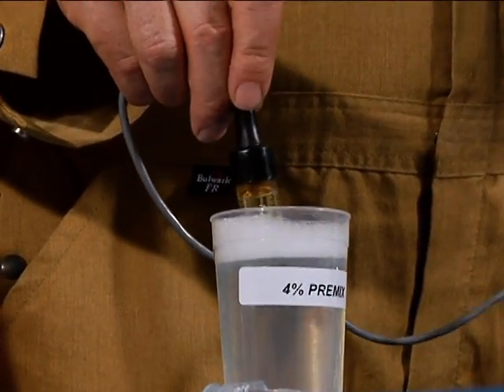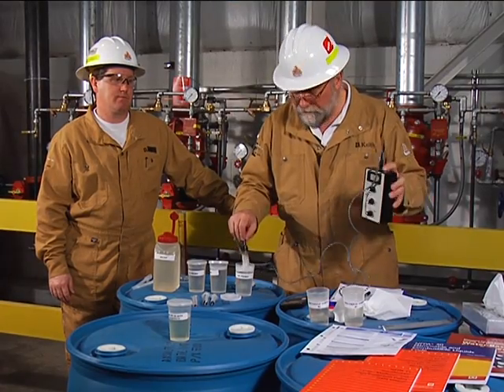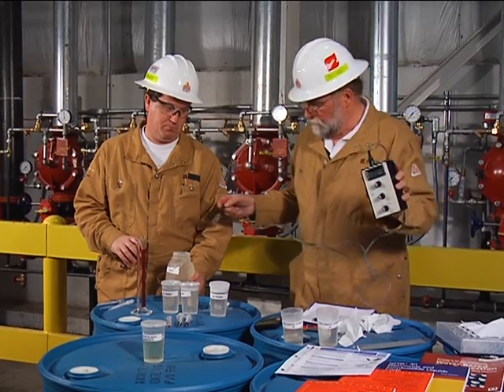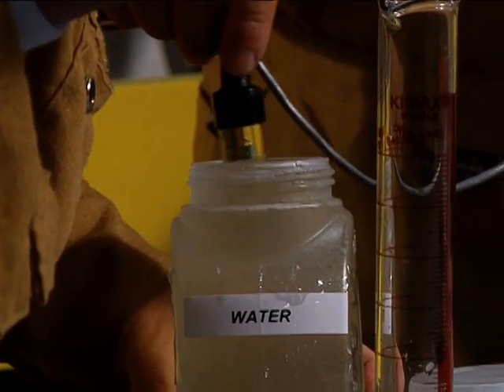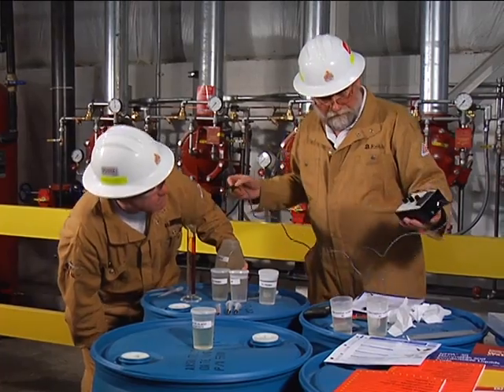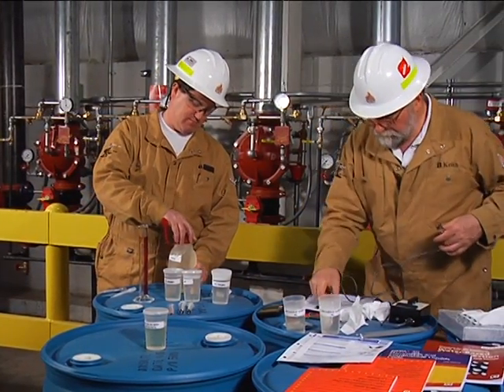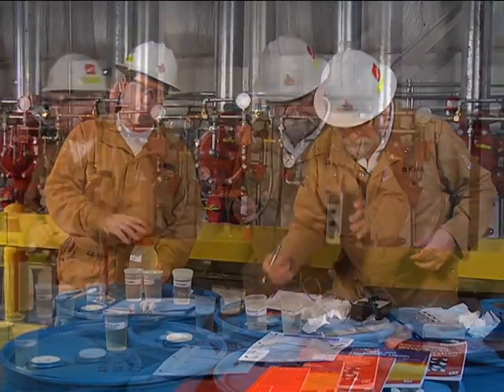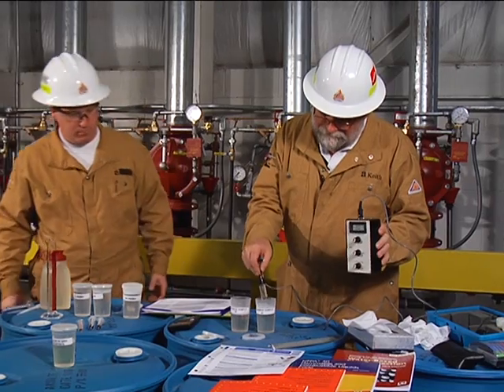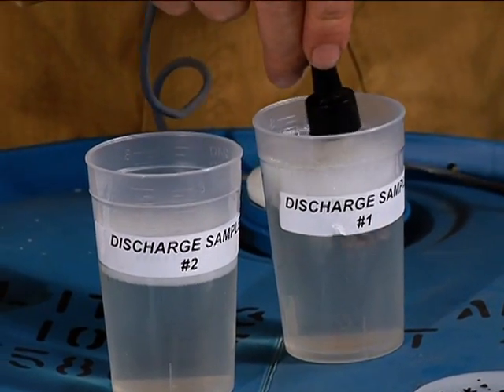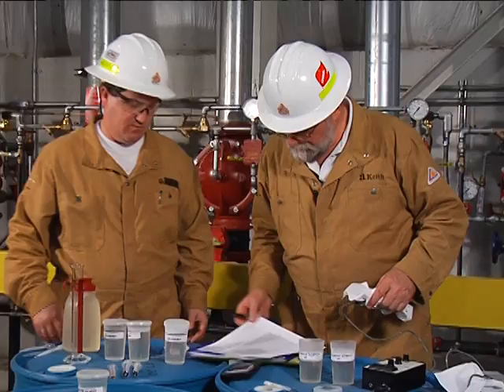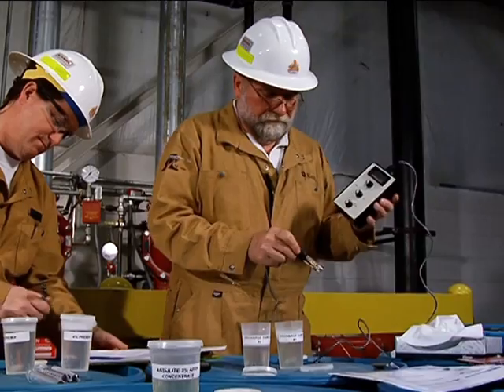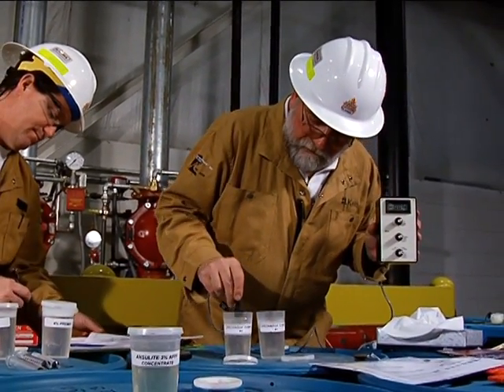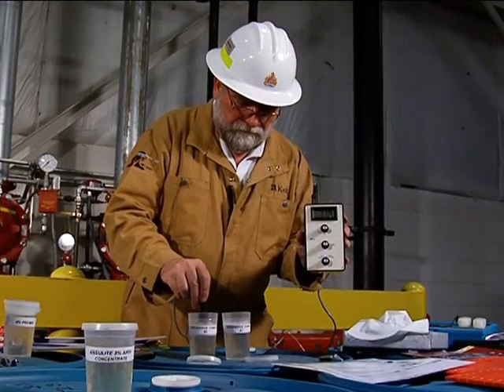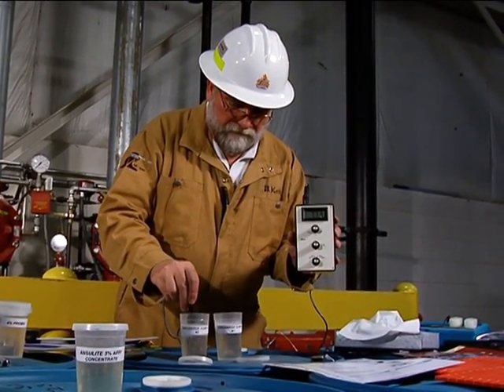And lastly, our 4% calibration standard. 8.90. 1.47. First discharge sample number 1. 7.75. Discharge sample number 2. 7.70.